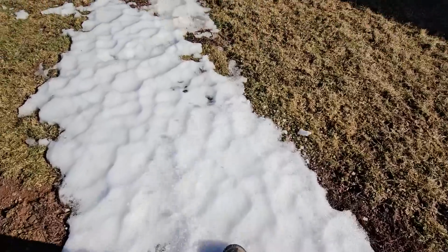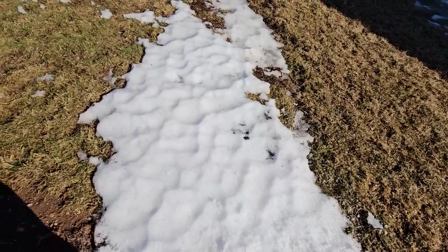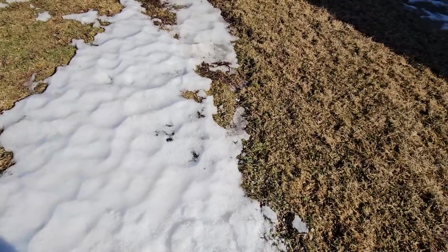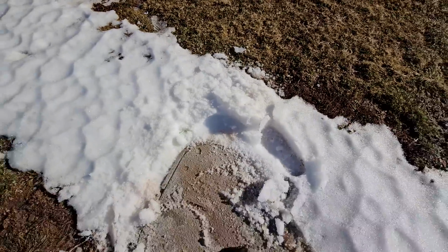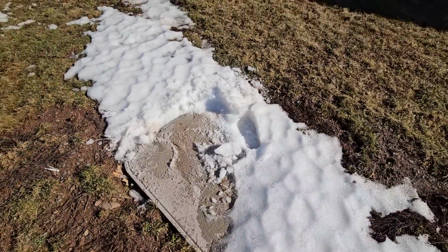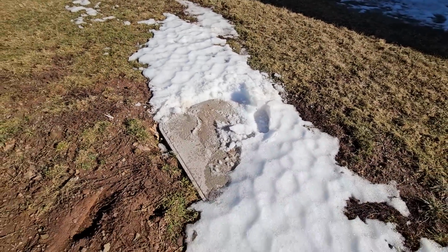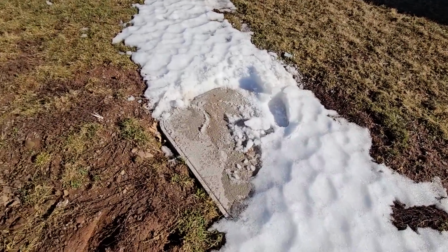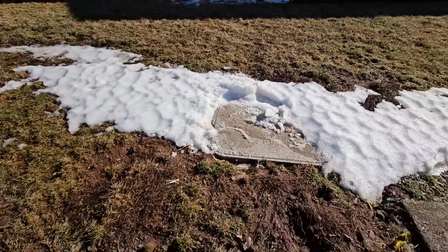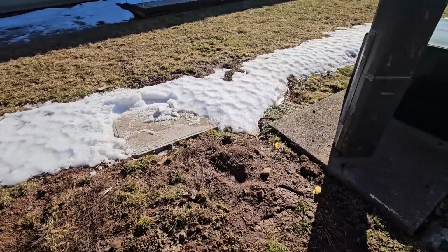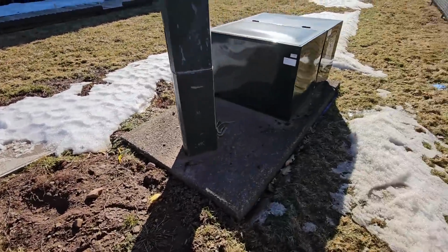This way the contractor was able to have his trenches and ducts all dug and prepared up to the URD box. We simply had to meet on site the day of connection, where he shoved a 90-degree PVC portion in, pulled his wires the rest of the way through, and we were able to hook those up all while energized without interrupting the other customers.